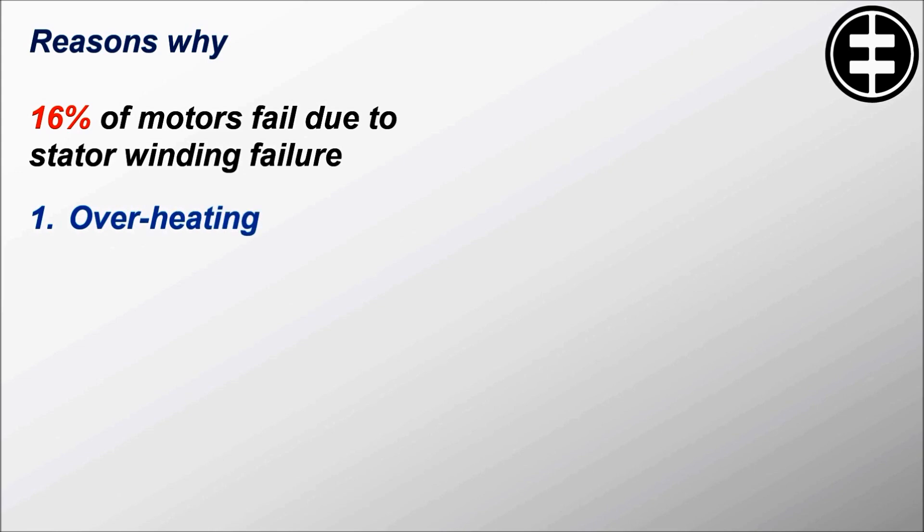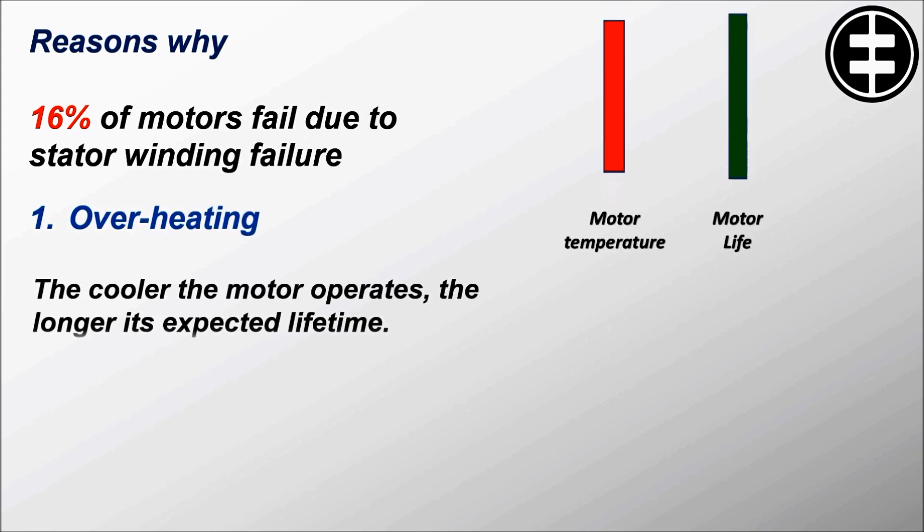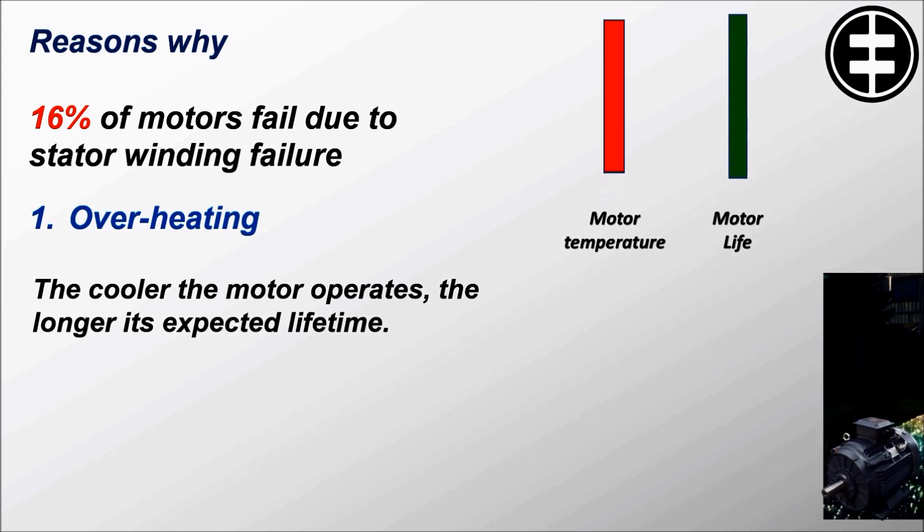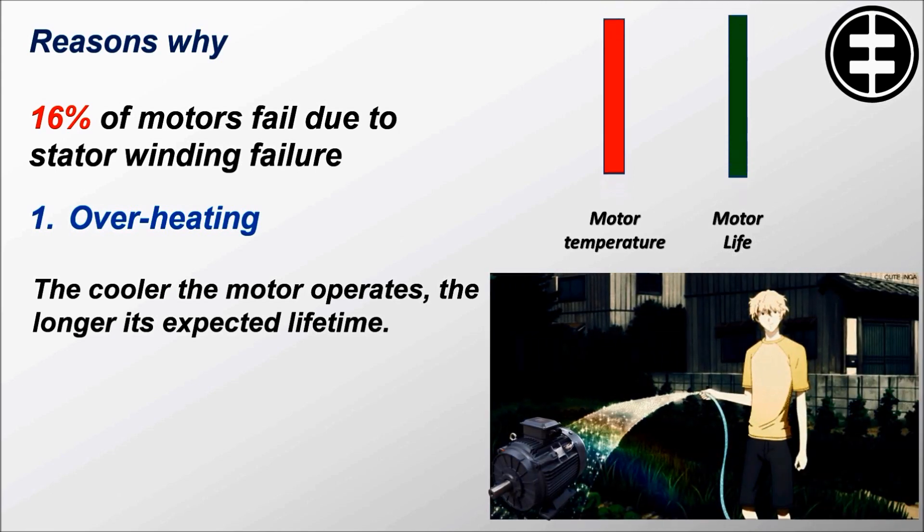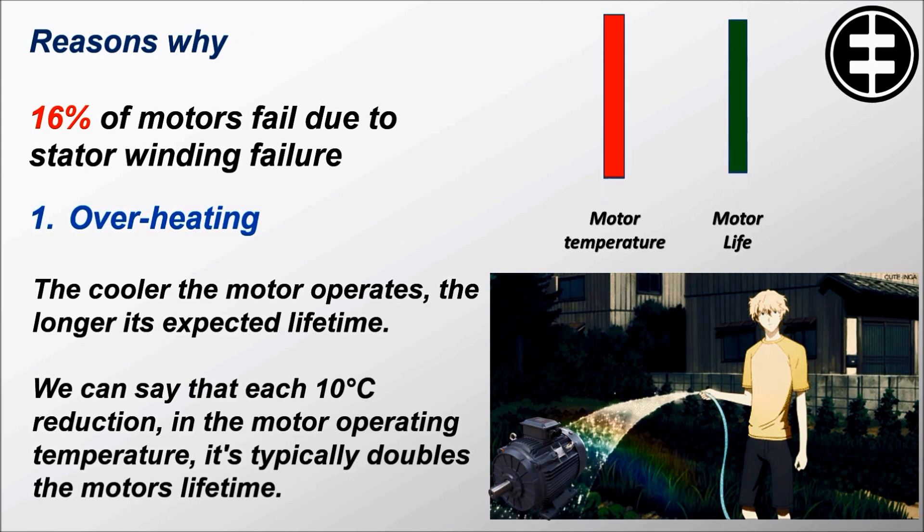Overheating. The cooler the motor operates, the longer its expected lifetime. So try to keep your motors as cool as possible. We can say that each 10 degrees Celsius reduction in the motor operating temperature typically doubles the motor's lifetime.